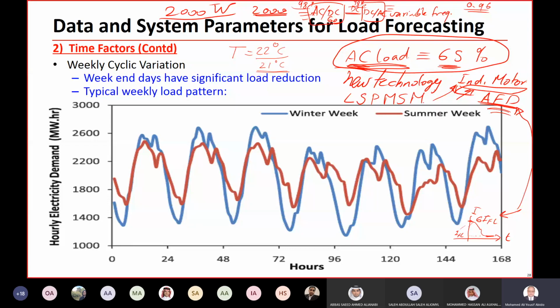Of course, you have to do a cost-benefit analysis. You have some losses in this conversion process, but what are the benefits if you have a variable speed drive? You can reduce the consumption of the load by like 30% or 40%, compared to about 4% of losses. Of course, your benefit is more pronounced than the losses introduced by the new installation or new devices.